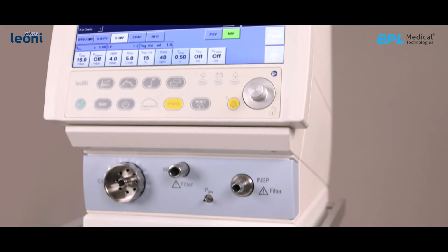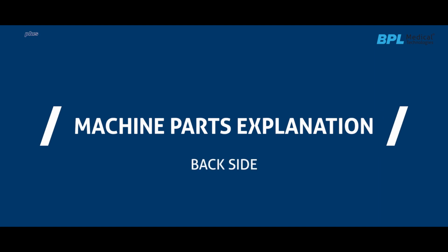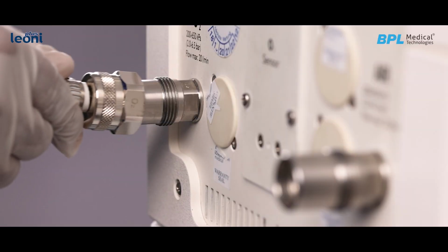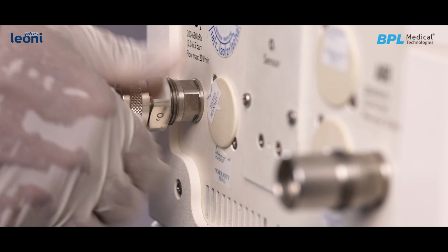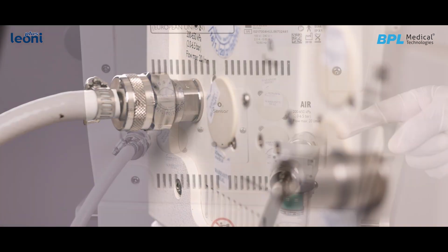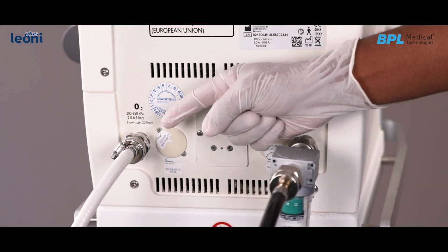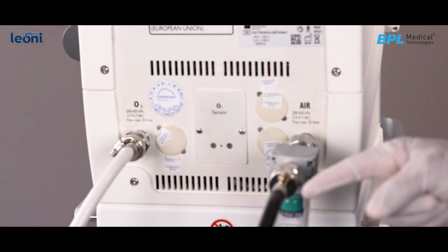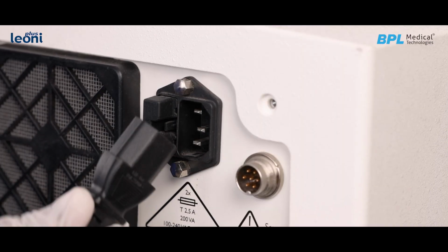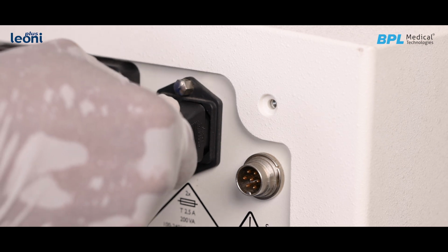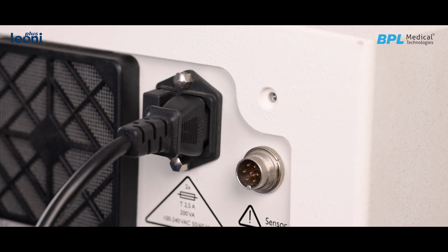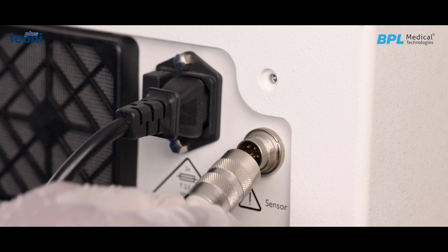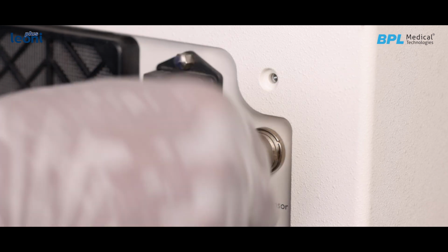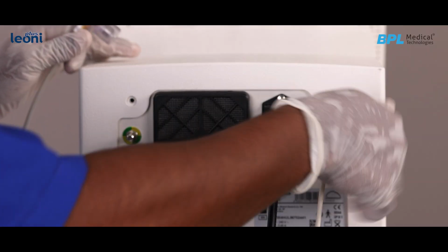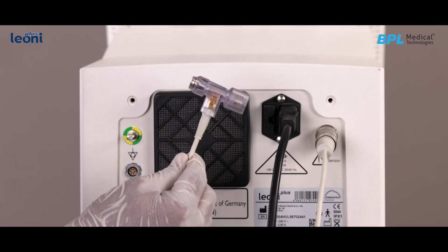Let us now have a closer look at Leoni Plus HFO ventilator. Gas supply connection. Leoni Plus HFO can be connected to central air and oxygen gas outlets. High-pressure color-coded hoses supply gases. Power cord connection. A 2-meter-long 2-pin power cord provides an easy reach to the power plug source. Expiratory flow sensor port connection. A proximal hot wire sensor can be connected to Leoni Plus by an extended flow sensor cable.